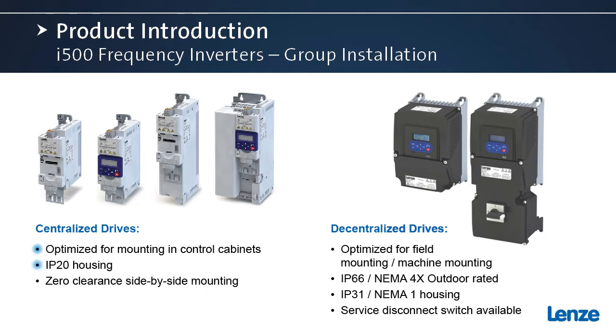They are IP20 housed, and a unique feature is that they do offer side-by-side zero clearance mounting. And so really zero space between the drives as they're mounted in the cabinet. And you can maintain the full 45 degrees C ambient rating with that zero clearance mounting. So really able to optimize the panel space using the centralized or cabinet drives.